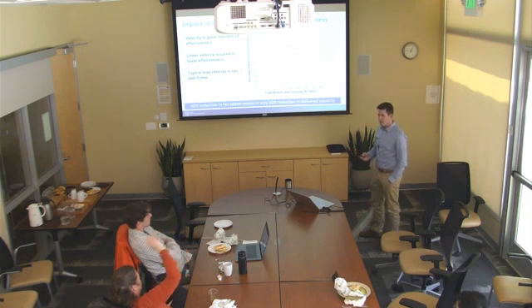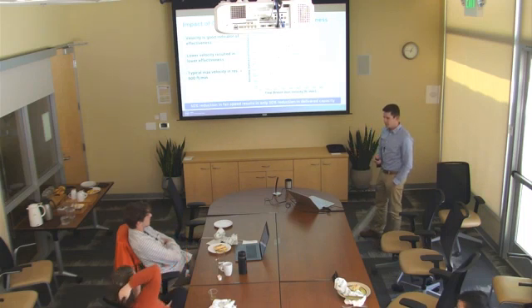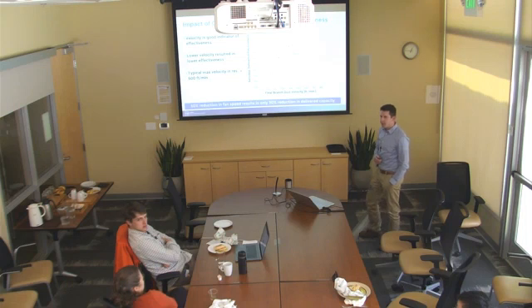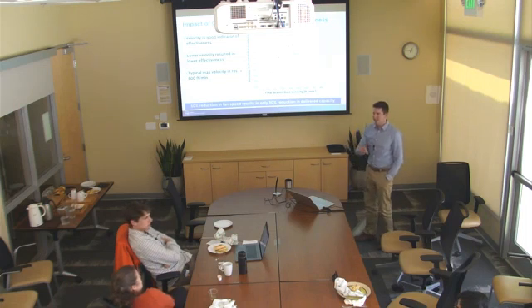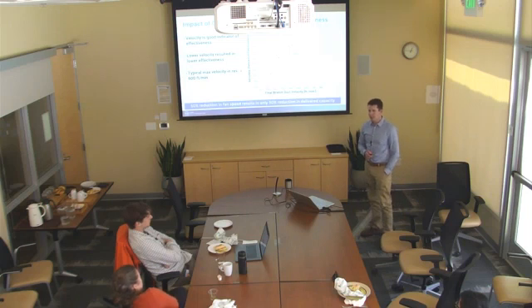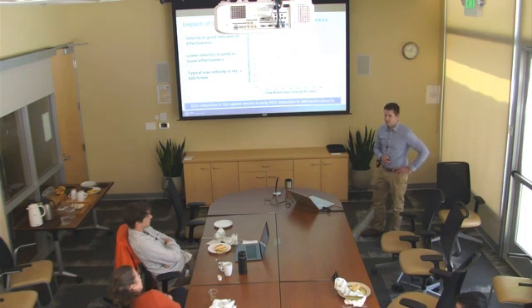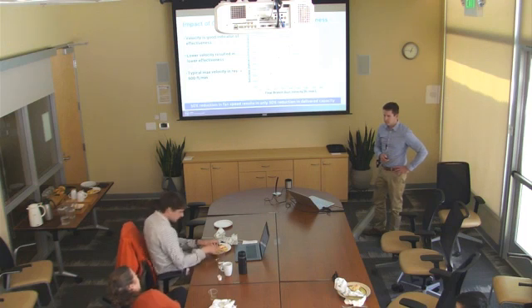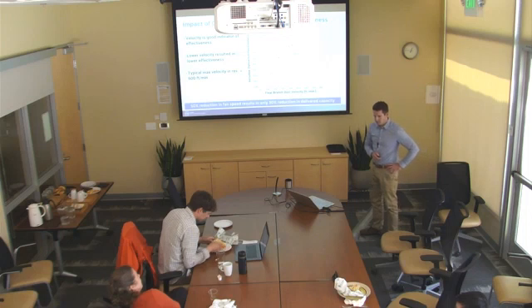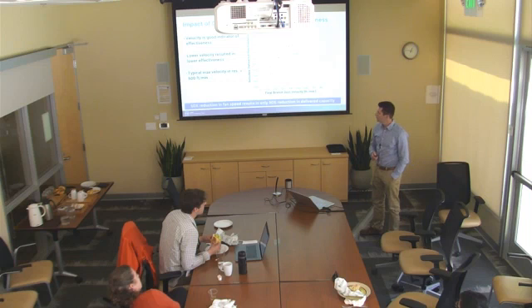So, is there any code requirement for this? Not that I'm aware of. There's Manual J, but it's more of a recommendation. I don't think there's a code or compliance requirement. I don't think that historically the Energy Commission has recognized that low velocities can consume excess energy, because you generally think, oh, my fan will have less resistance. Sure. And in fact, the Energy Commission may essentially work against itself because it keeps lowering the allowed watts per CFM for your fan, so people oversize their duct system. Yeah, sure, that's a good point.